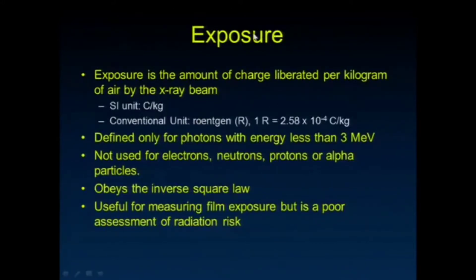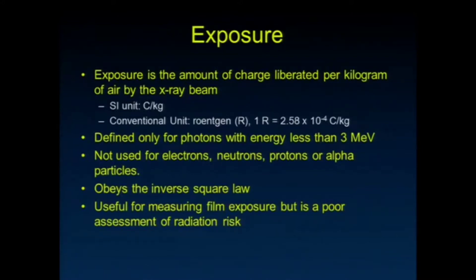Exposure is the amount of charge liberated per kilogram of air by the x-ray beam. It was one of the first quantities developed because measuring it was relatively straightforward — you put a small ionization chamber with air in it, place it in front of the x-ray beam, and measure how much charge was liberated by measuring the current that flowed across the anode and cathode of that ionization chamber.